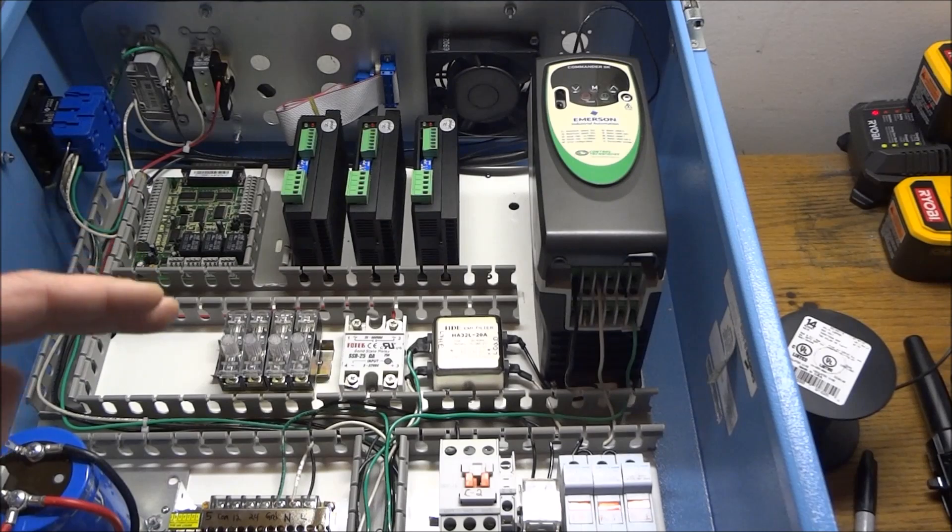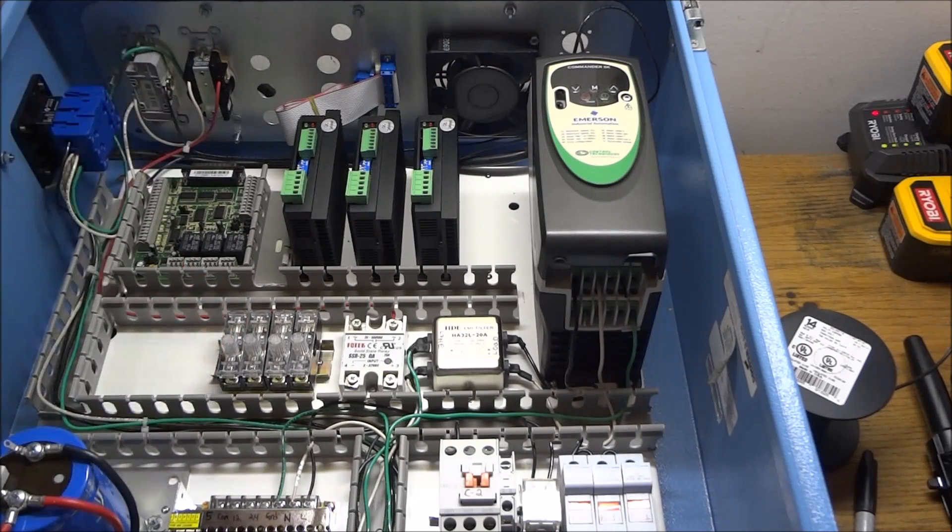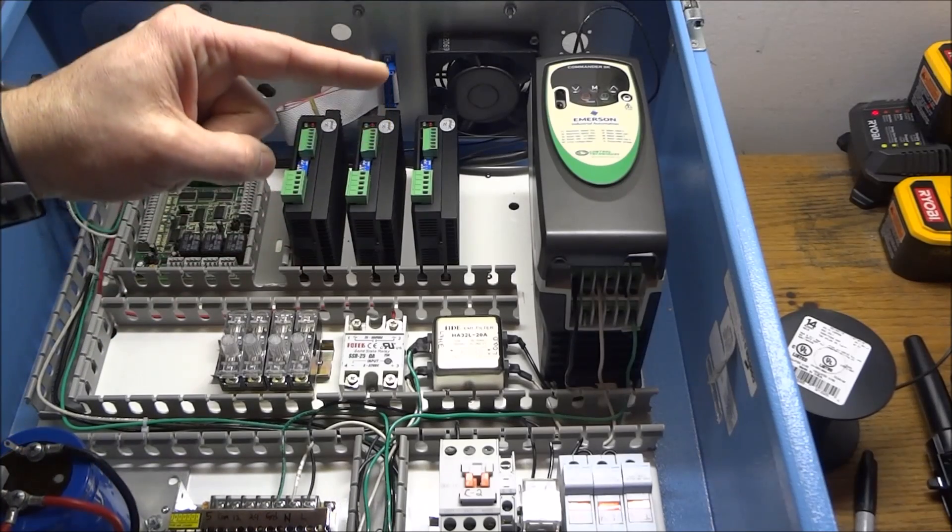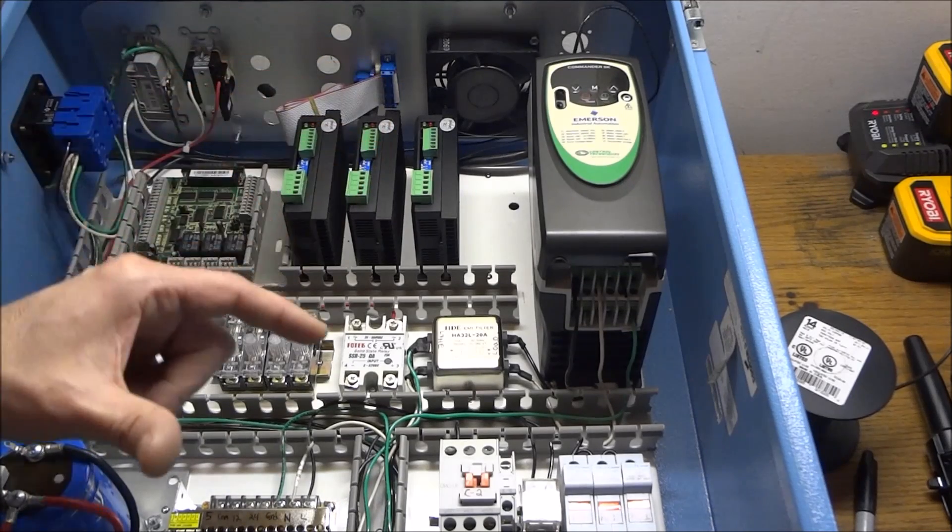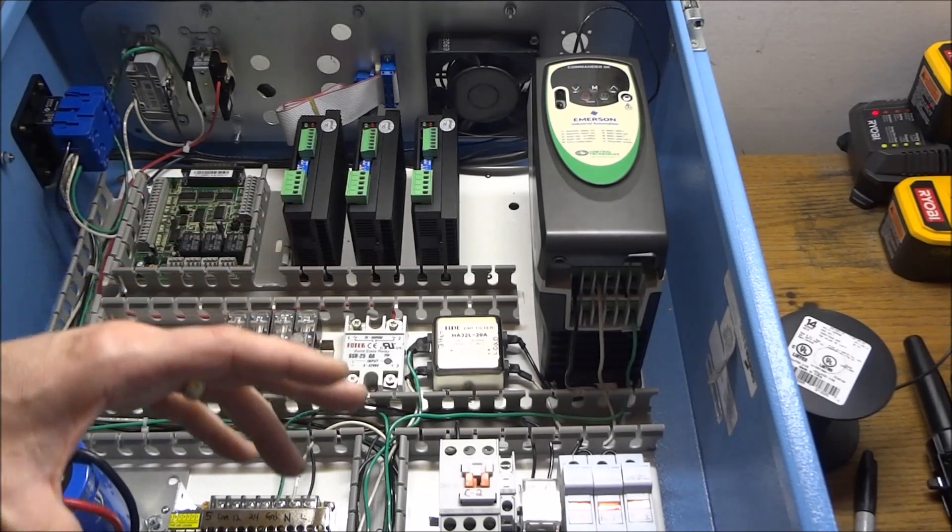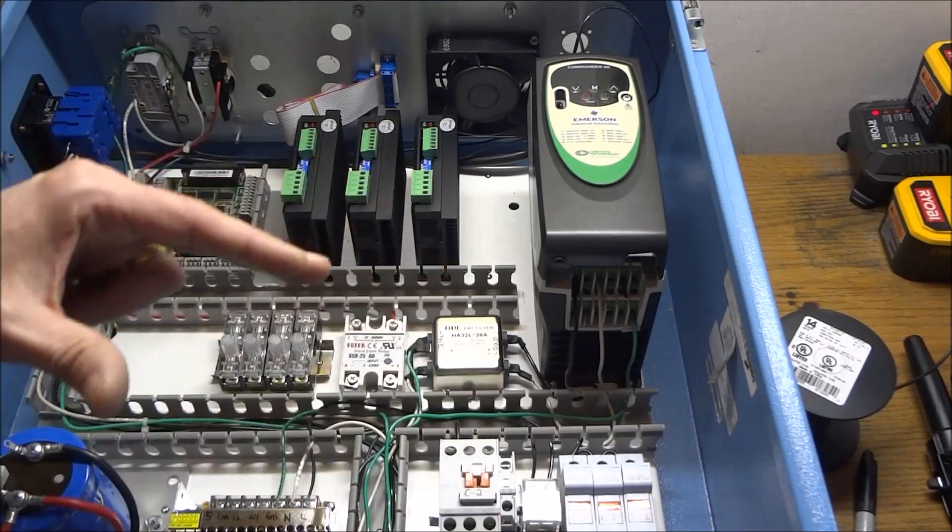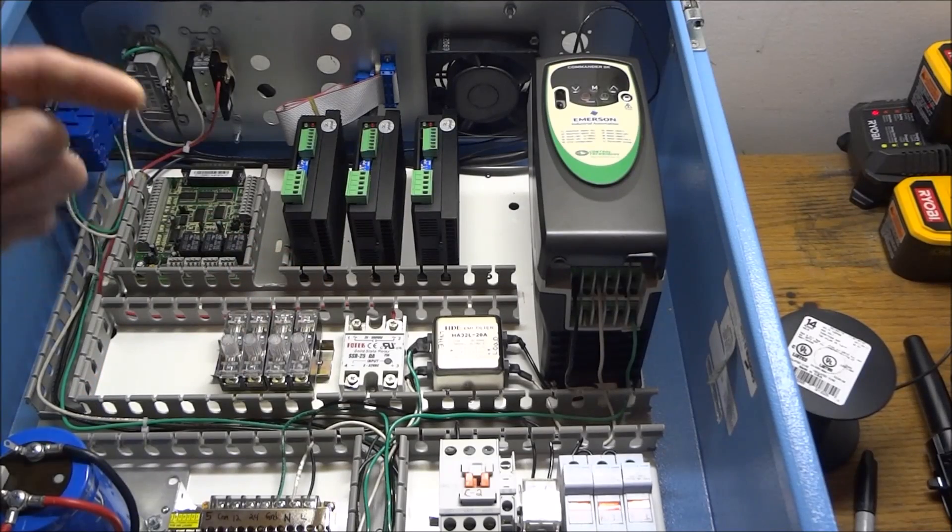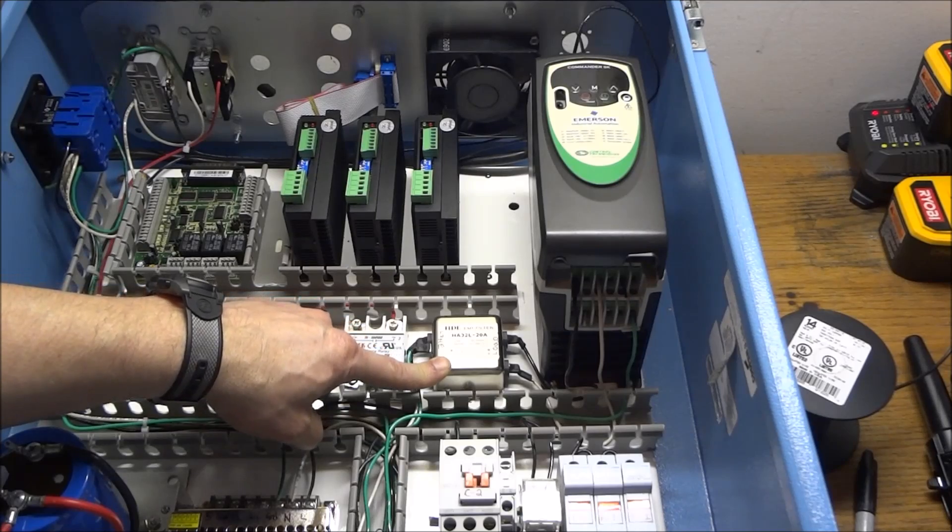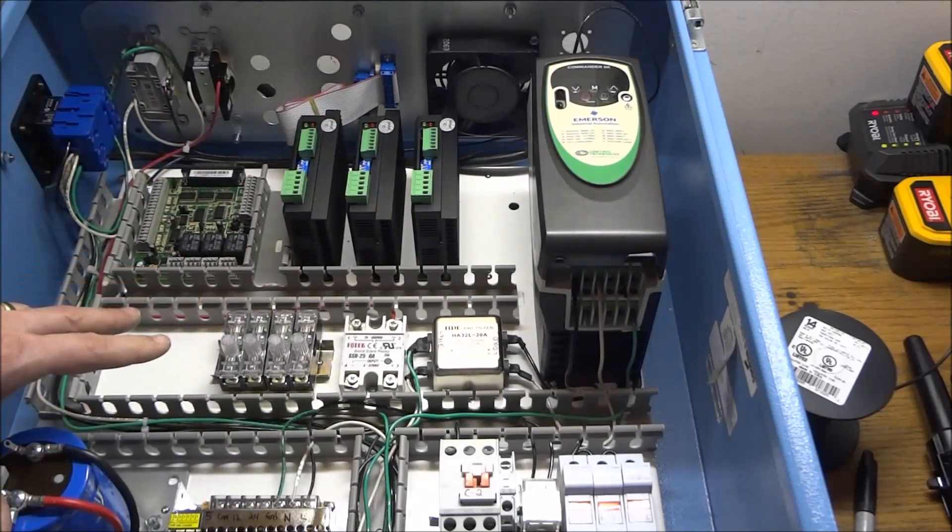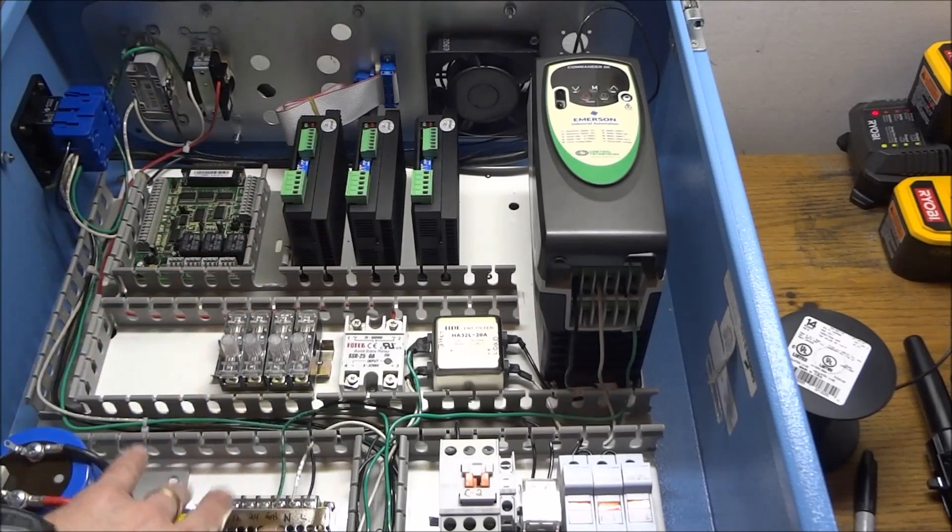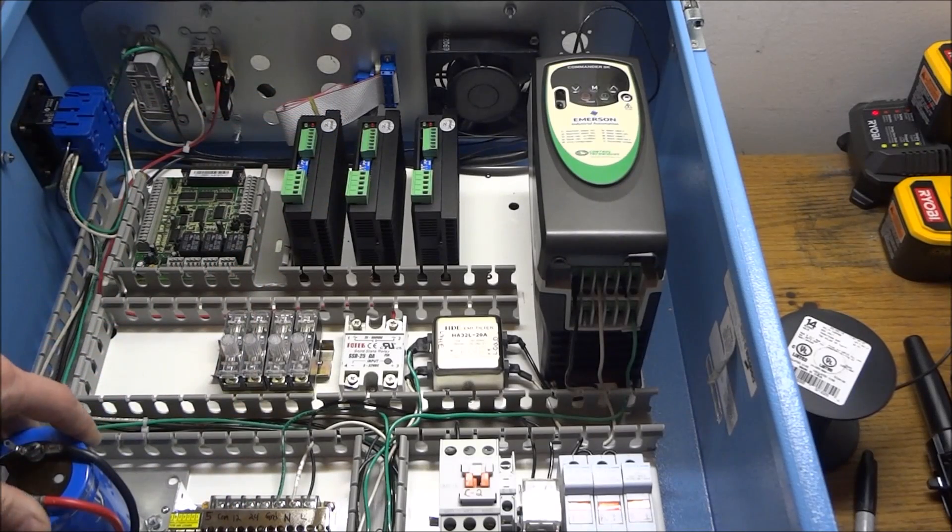Now what the filter does is it filters out the incoming power. And then when the VFD generates the EMI and it tries to come back to the source which is the VFD, the EMI filter prevents this noise from getting back into your system and getting back into your power supplies and your electronics.